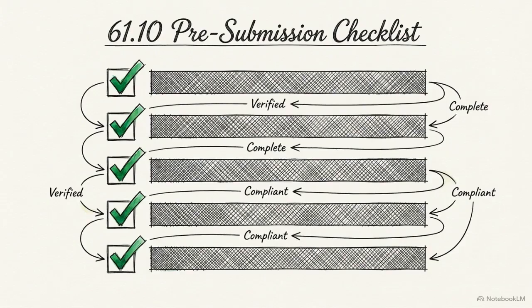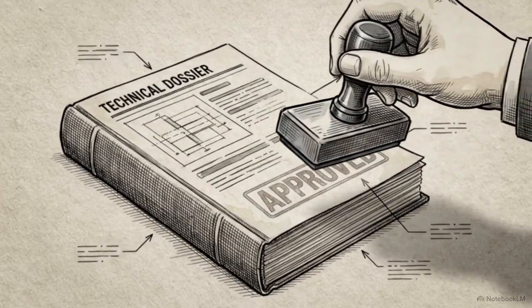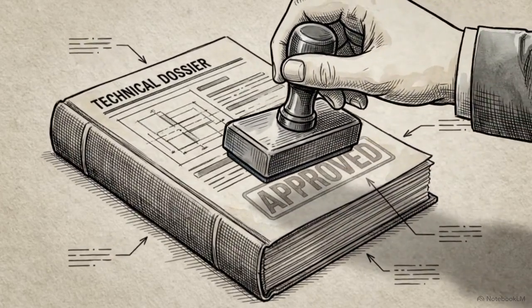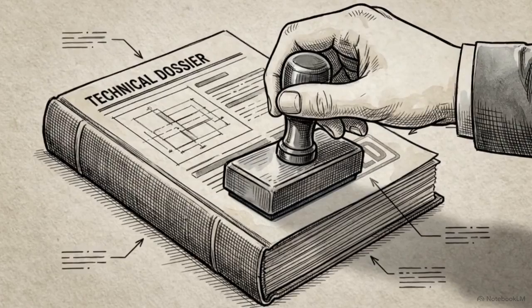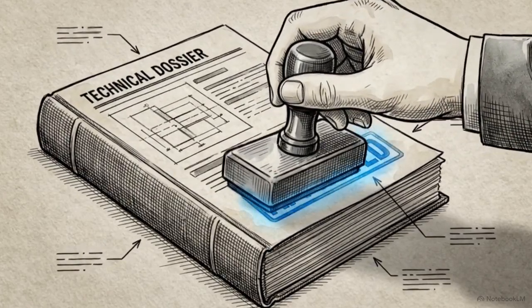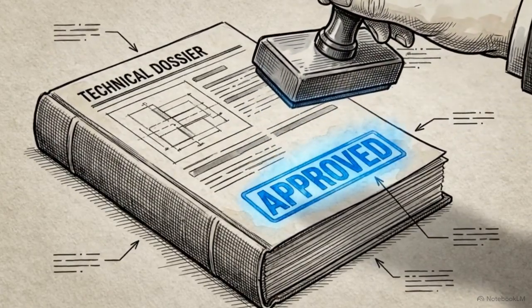Before submission, verify 5 criteria. Parameters are non-clinically testable, 0 clinical claims, predictable biological responses. Risks mitigated via bench tests, no specific post-market trials. Once these conditions are met, the submission is verified. A successful 61.10 justification depends on engineering undeniable, logical proof of safety from the ground up.